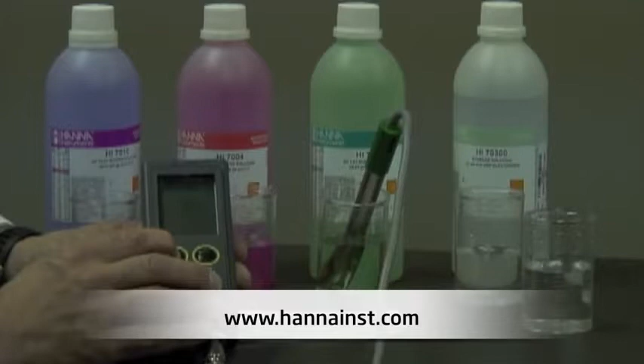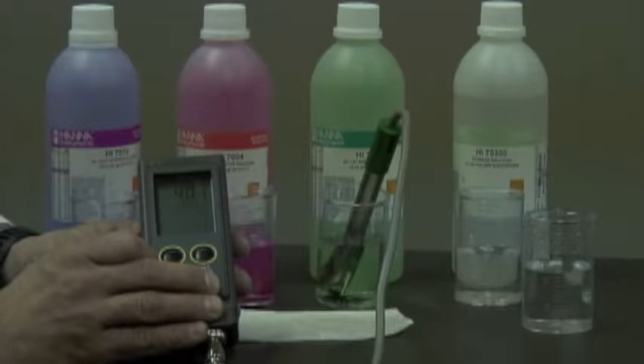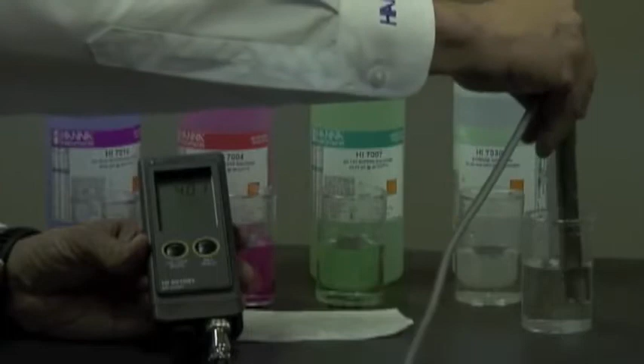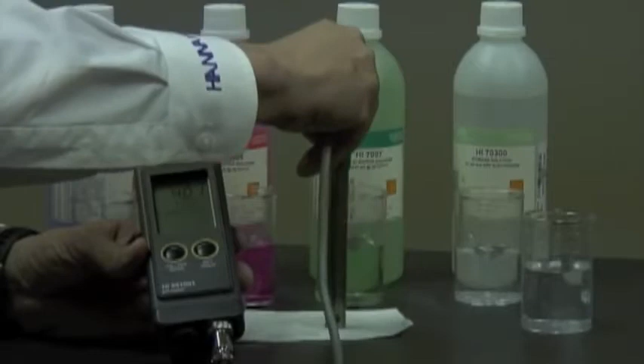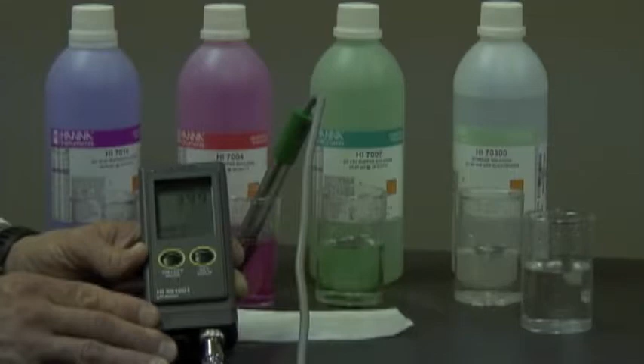Once it goes into its measurement mode, I'm going to hold down the left-hand button for 3 seconds until it goes into cal, and I'm going to let it go. Now, it's asking for 7, so I have the probe in 7, and once it recognizes 7, it's going to ask for 4. So at this point, if I just wanted a 1-point calibration, I could hit the left-hand button and go back into the measurement mode. Or if I want a 2-point calibration, I can put it into a 4 or a 10. Okay, now it's recognizing 4. Okay, now we're back in the measurement mode. Next, I'd like to show you some of the setup features.